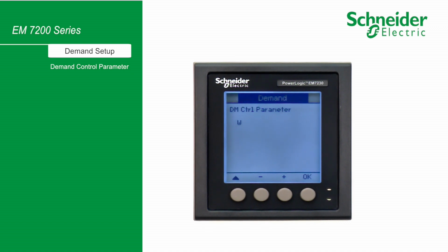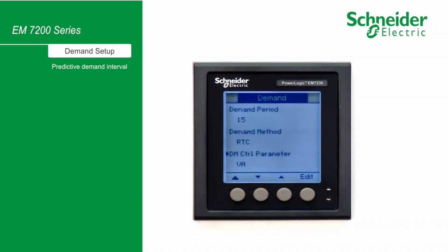Your demand controller has the ability to forecast the demand values well in advance. It follows a complex and proven demand calculation algorithm to predict the demand and enable you to manage your load. Prediction demand interval could be 4 to 7 minutes if the demand interval is 15 minutes, and when the demand cycle is set for 30 minutes, the prediction demand could be 7 to 15 minutes. Prediction demand interval can be set from 1 to 30 minutes. Let's select 7 minutes, then press OK.